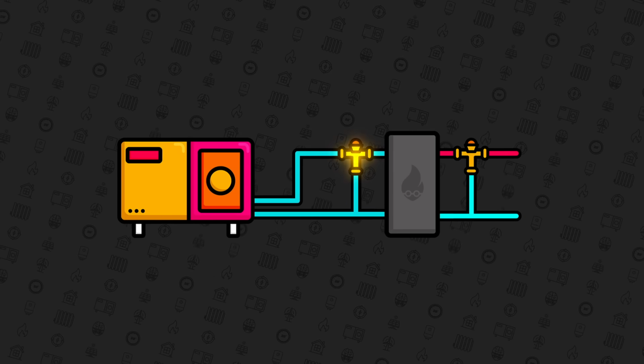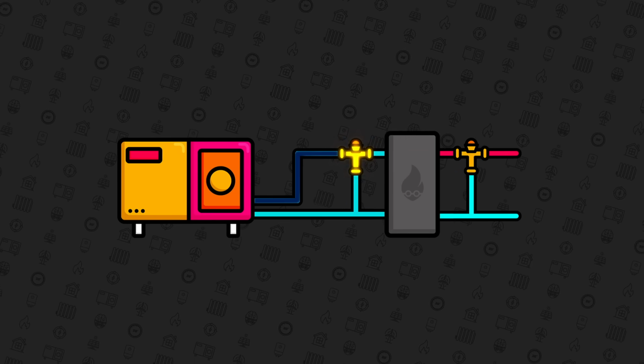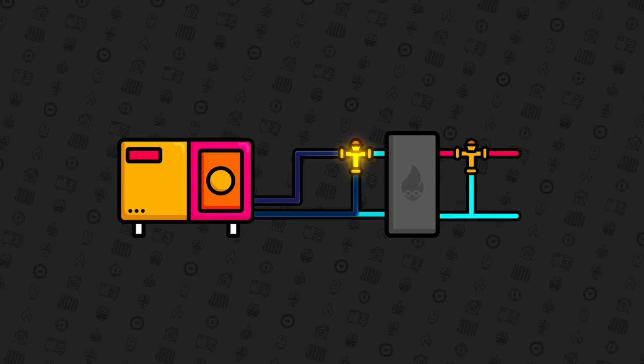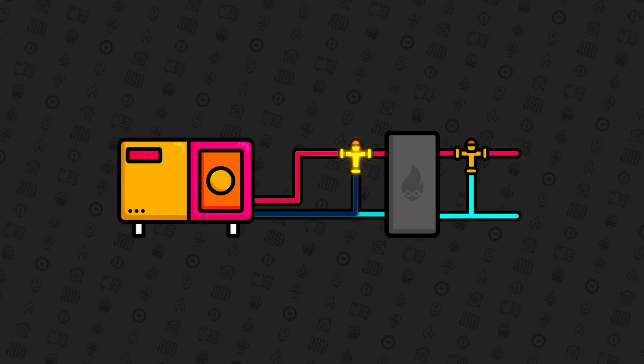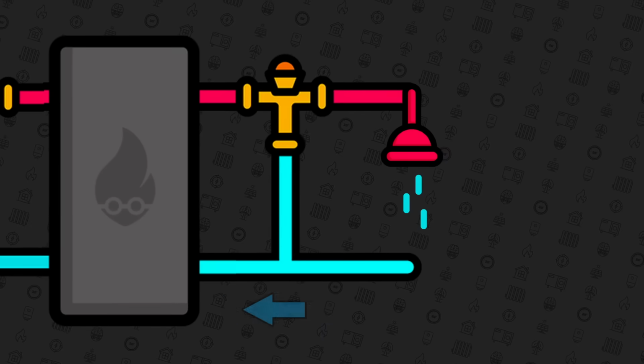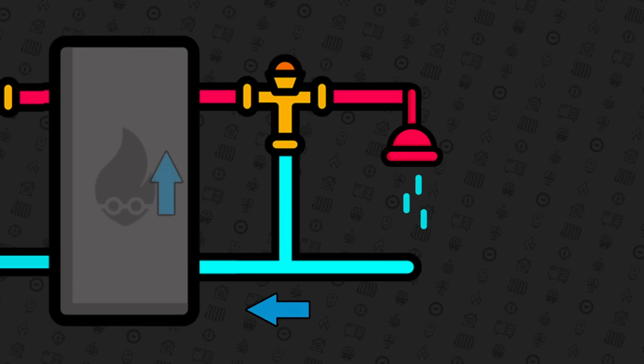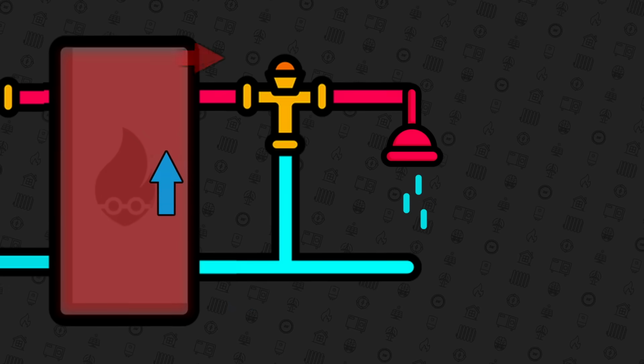To prevent the other problem of the store being cooled while the heat pump is warming up, a second blending valve on the heating side of the plate will only open when the heat pump flow temperature finally reaches 45 to 55 degrees Celsius. And this allows the primary pipework and the heat pump to preheat itself and charge up with energy before beginning to open up to charge the plate heat exchanger. This kind of acts like an additional 7 to 10 litres of stored heat to boost the plate while it's in use. So, cold water comes into the heat exchanger here, heats up and leaves hot here.